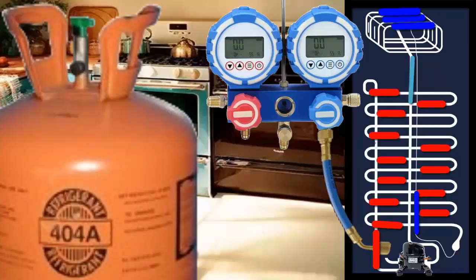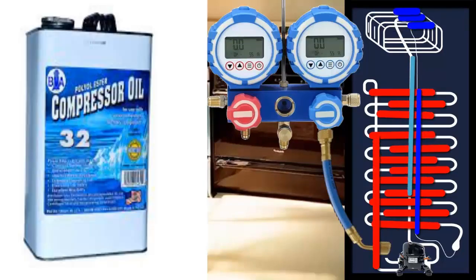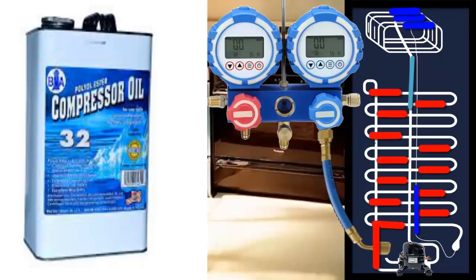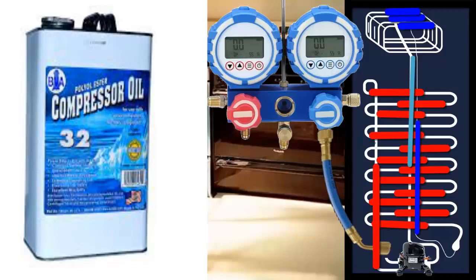The R404A operates with POE-type oil. The most commonly used viscosity for oil with R404A is 32 centistokes, although it will ultimately depend on the compressor manufacturer.